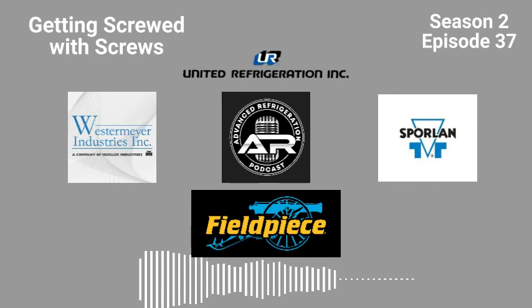These guys were having trouble figuring it out. So I go over there and I'm looking through it. We changed the cable, and I'm like, okay, if I disconnect the cable, I got it. I'm like, okay, this is weird. So I start tracing it back, and I pull the white wire off the controller, and I throw my meter on there, and I go to black, and I'm like, okay, I have the power. Put it back on there, no power. So it was all because it wasn't configured for the CPC sensor then. And it wasn't. They never pushed the program originally when they programmed it.